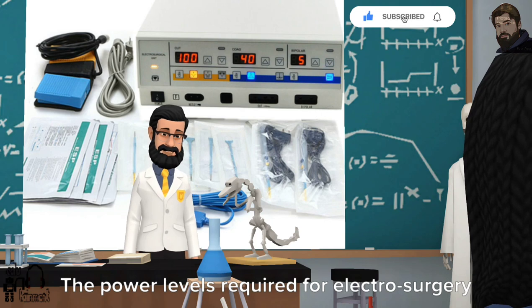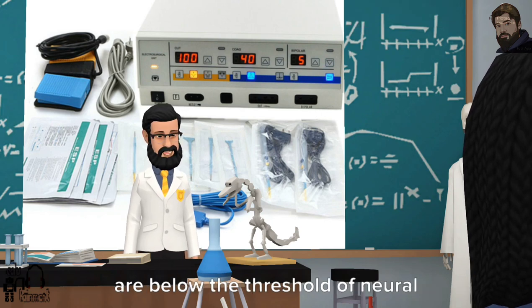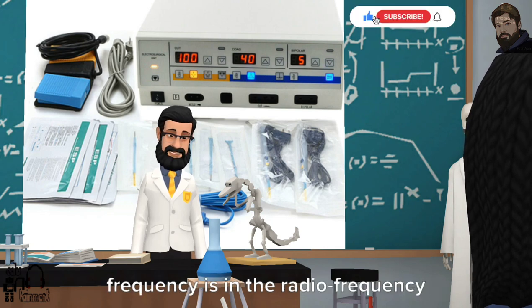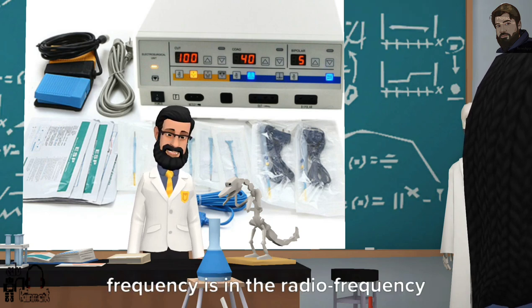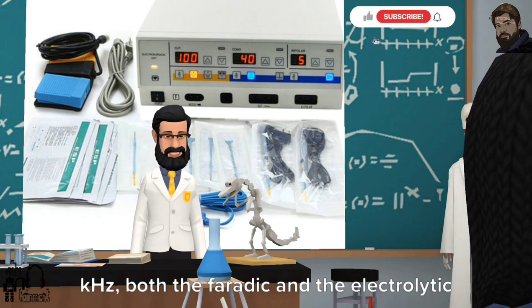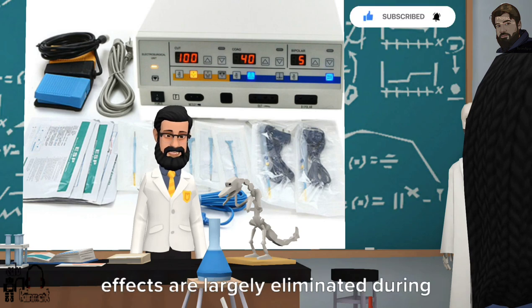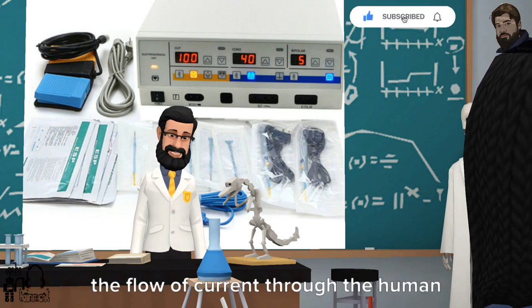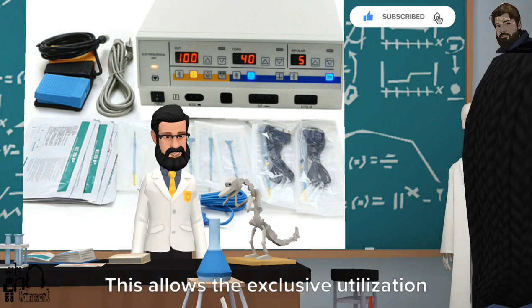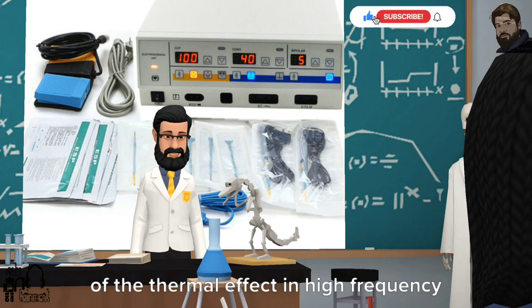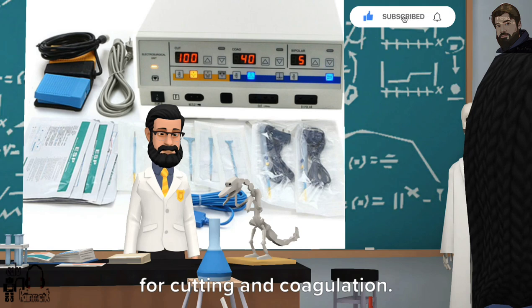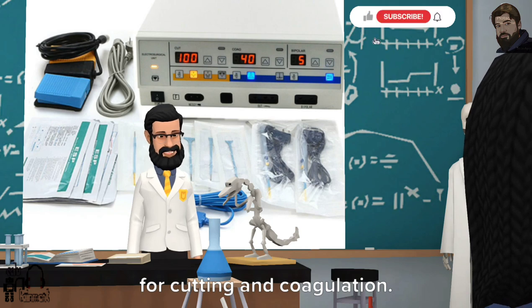The power levels required for electrosurgery are below the threshold of neural stimulation provided that the diathermy frequency is in the radio frequency range. When the frequency is at least 300 kHz, both the Faradic and the electrolytic effects are largely eliminated during the flow of current through the human tissue. This allows the exclusive utilization of the thermal effect in high frequency surgery providing both the applications for cutting and coagulation.